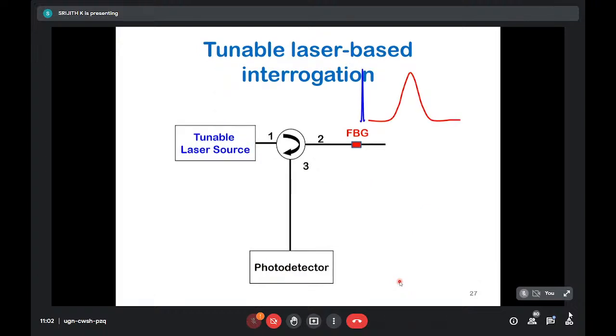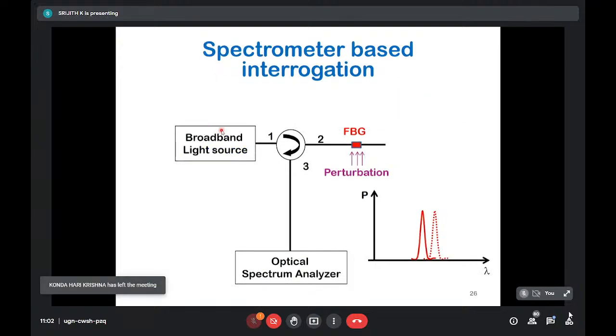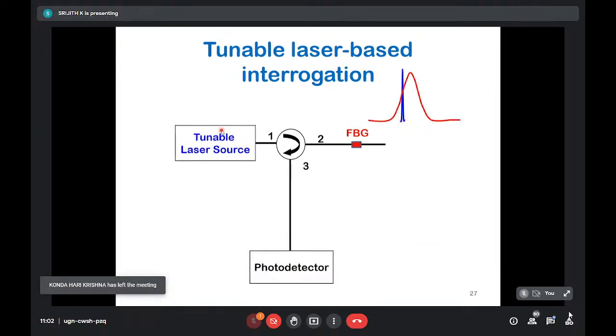Okay, so there is another technique where you don't use a spectrum analyzer. Rather, you use a simple photodetector, which is very cheap, but then you use a tunable laser source. Okay, in the previous case you saw that you were using a broadband light source, probably an LED source, but now you're talking about using a tunable source. Okay, so when I say tunable laser, we are talking about a very, very narrow line width, narrow spectrum laser. And what you do is you bias your tunable laser on this reflection slope of the FBG. So you can see that the tunable laser is biased at the slope, and it's only that much light that gets reflected back into the photodetector. Okay, so it is a very small amount of light that reflects from the FBG.